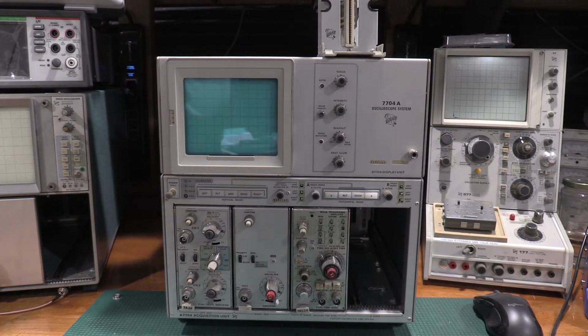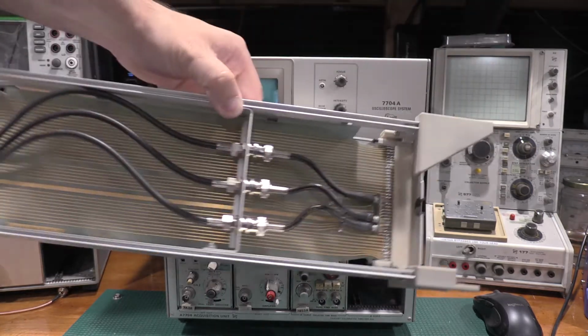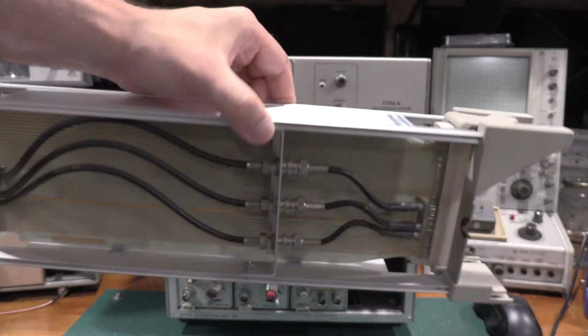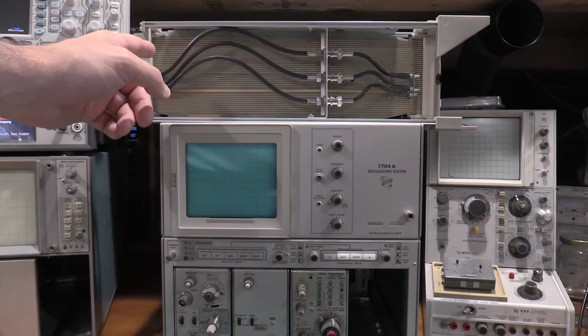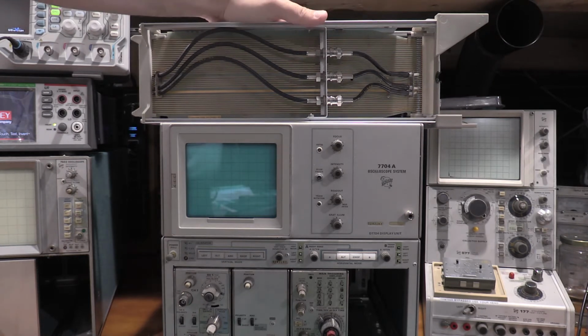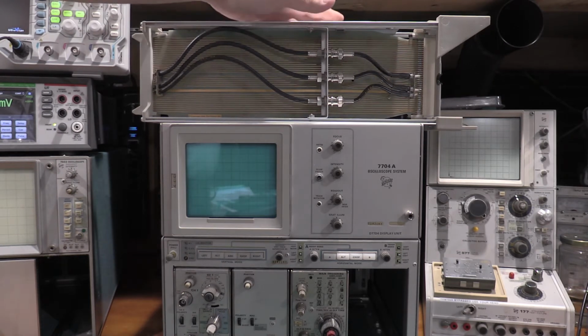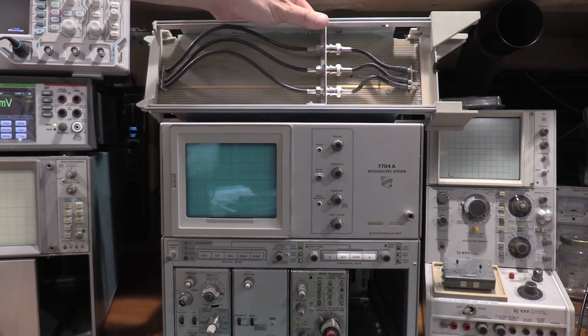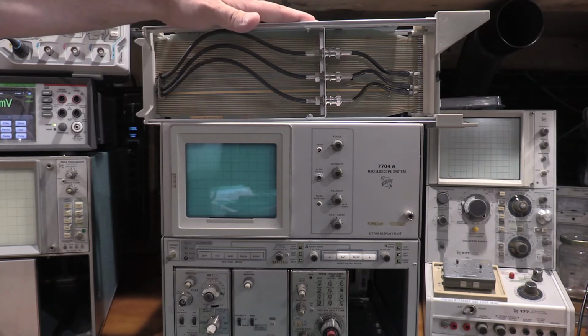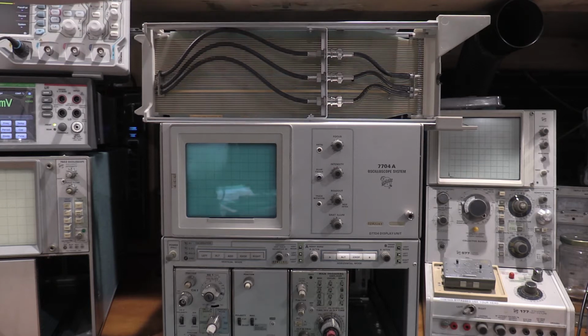To do this calibration, unfortunately, you will need the extension, either the flexible extension or the hard extension. I have the hard extension, so I'll be using this extensively for this calibration. If you're lucky, you can find these on eBay. They tend to not be inexpensive. These go for about $200, these frames, but fortunately, I've never needed more than one to do any of these, so everything will be good. So let me get the service manual printed out, and we'll get started.